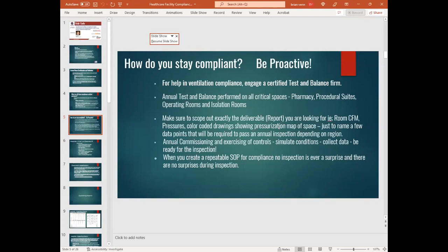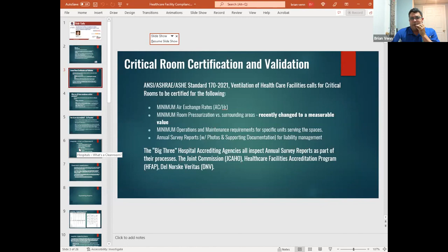I will just pop up to where I was talking about those first couple of slides for a few minutes. The critical room verification, again, we were working our way down to what is actually classified as a clean room. And clean rooms have many different levels of classifications. With each classification comes different pressure requirements. Clean room classifications are based on the amount of particles that may be allowed per cubic foot in a room. And then you can find a lot of these standards and acceptable levels in the ASHRAE materials.